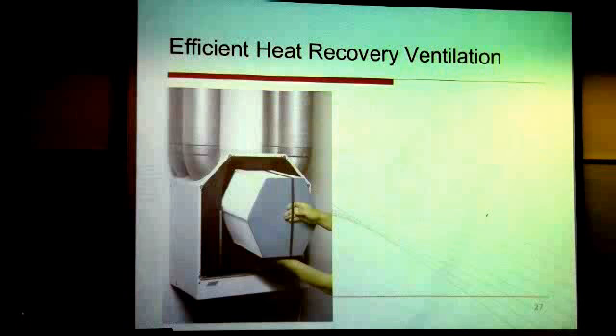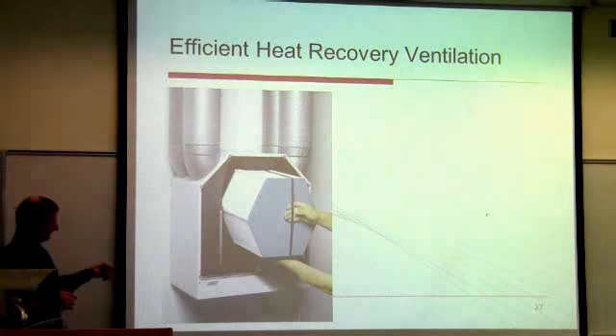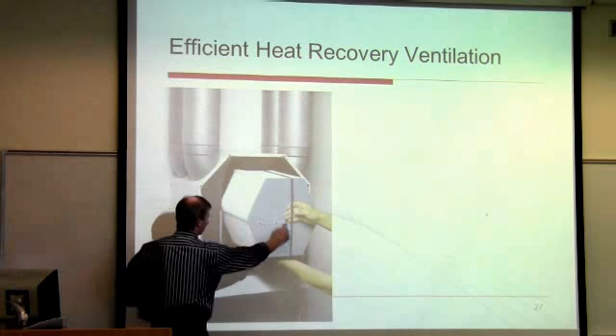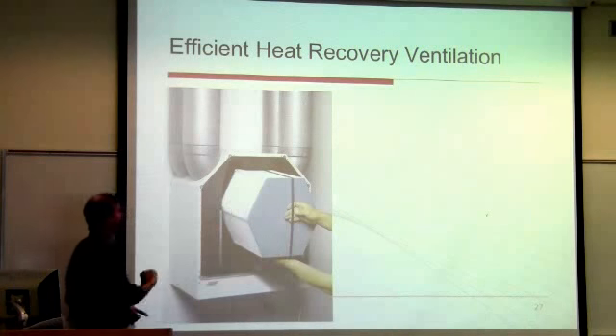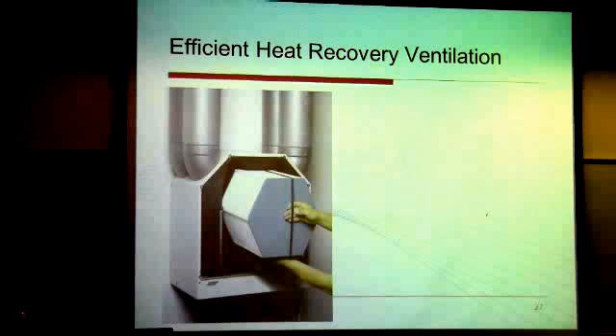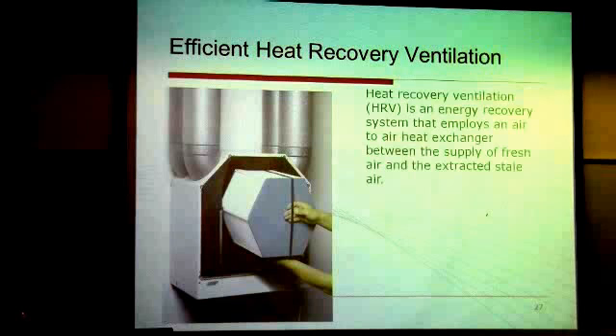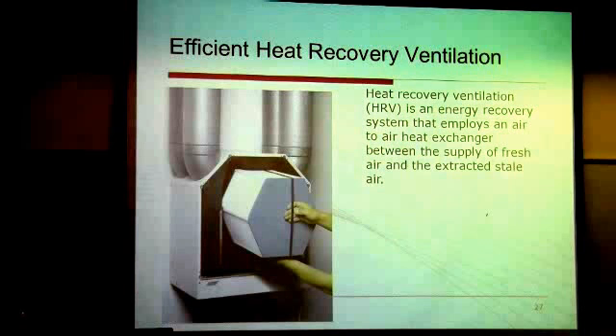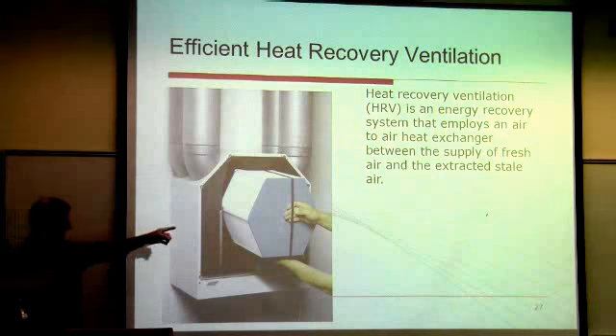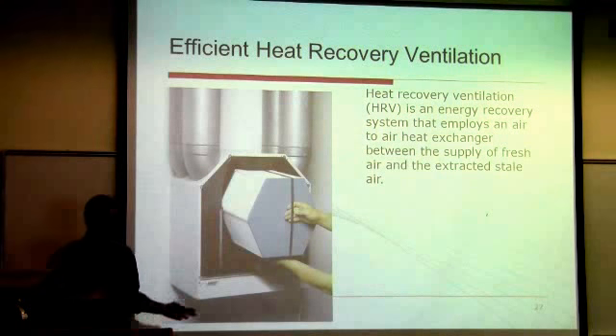This is a system that's in that duplex and the other houses we talked about. It's kind of a combination hybrid where it's going across in a counterflow, where air comes in here, goes across, and then out, and they pass. So it gets a little bit more efficient than other types. So to your question, heat recovery ventilation is where you're recovering the heat energy when you're exhausting that heat, and it's coming across this heat exchanger.